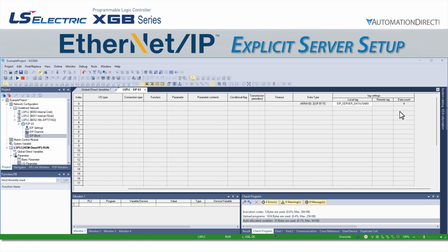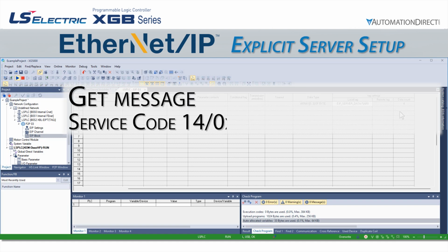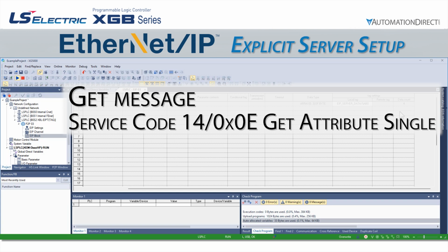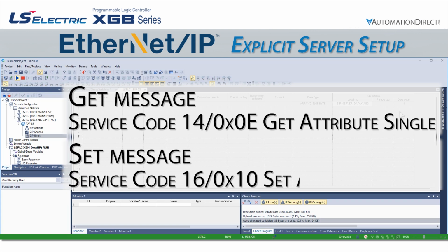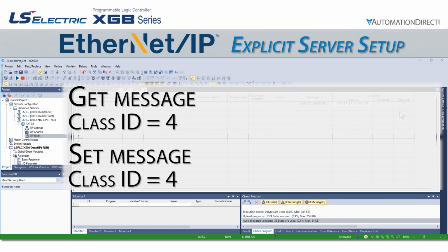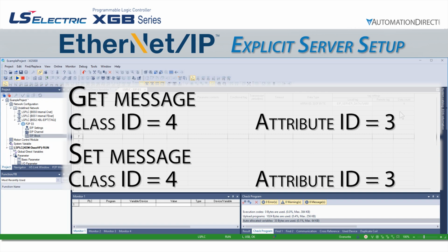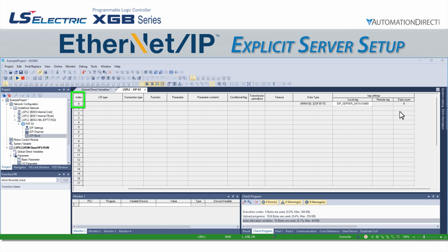The primary difference between this data being accessed by an implicit scanner and an explicit client is in the data location. The explicit client will be able to access this data by using service code 14 or hex 0x0e get attribute single for reading information, and service code 16 or hex 0x10 set attribute single for writing. The class ID will be 4 for both, and the attribute ID will be 3.